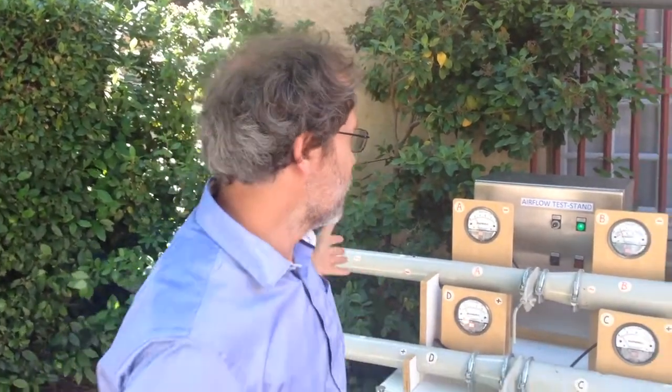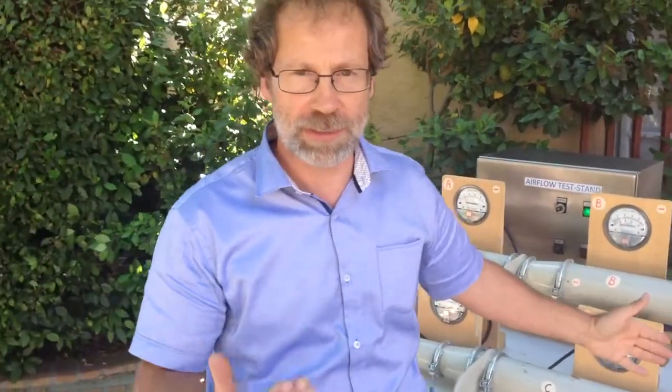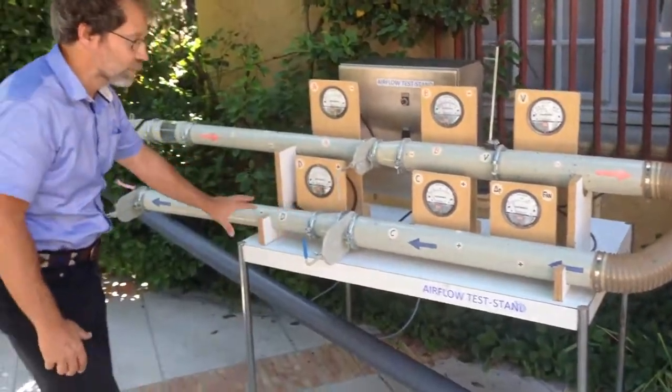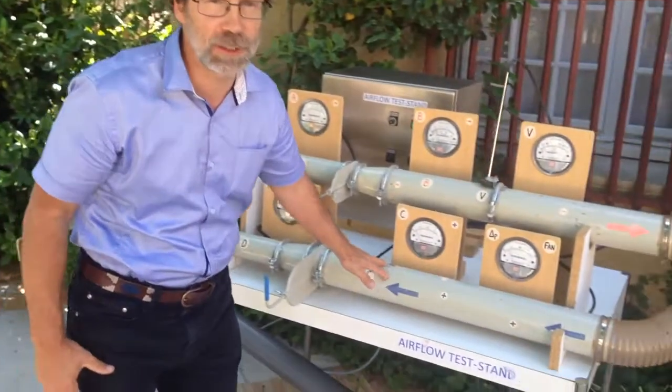As the next thing, I will talk a little bit about pressure drop and static pressure measurements. Basically, when we talk about static pressure, it could be a negative value or it could be a positive value. In this particular system, at the suction side of the fan, we will talk about vacuum, which is negative static pressure. And on this side here, after the fan, since we are going to atmosphere, this part of the duct system is under positive pressure.